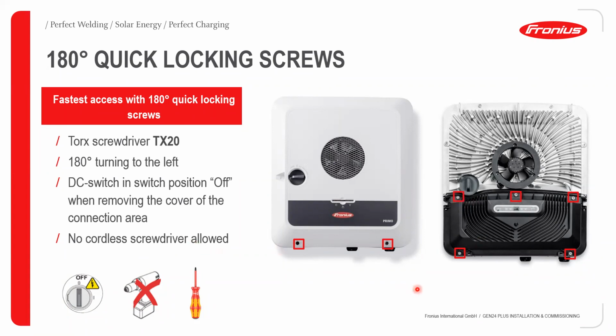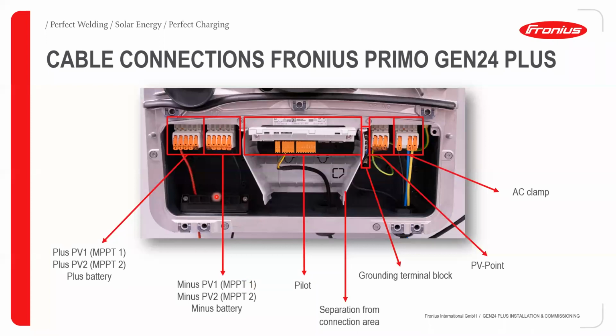You have 2 of these screws on the inverter cover and 5 on the DATCOM cover. This black covering is what we call the DATCOM cover - DATCOM meaning data communication - and this covering protects the DATCOM area. Once you unscrew these 5 screws using a Torx 20 screwdriver, you'll have access to the cabling area, as you can see.